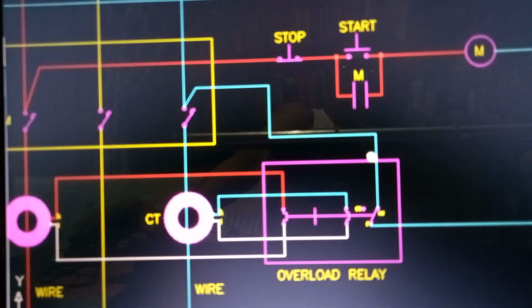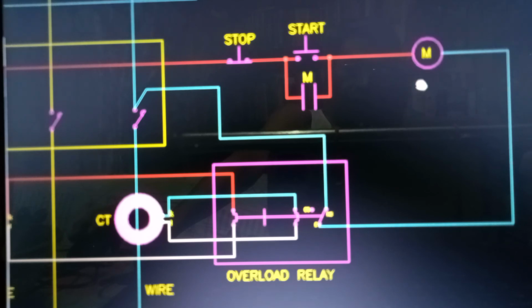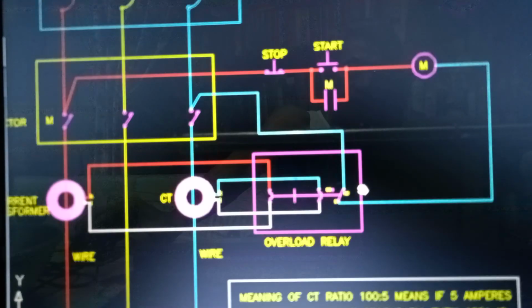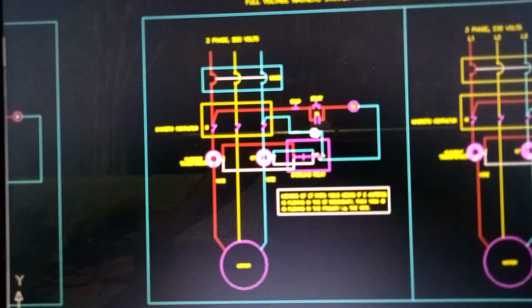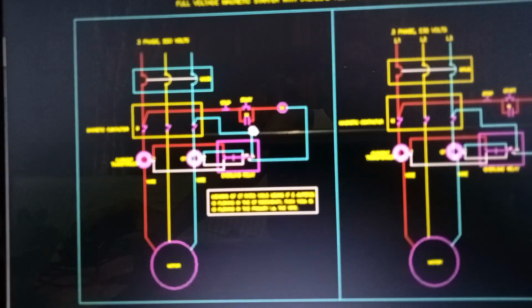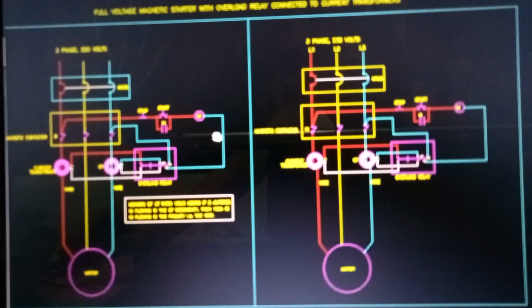The holding circuit interlock is a normally open contact of the magnetic contactor. So this normally open contact will close, and if you remove your finger from the start button, this will be open again. And since this is already closed, it will bypass the start push button, and the current will flow through here to the holding circuit interlock and then to the coil. And then from the coil, it goes to the normally closed contact of the overload relay and back to line 2. So that is the wiring of the schematic diagram of the full voltage magnetic starter.